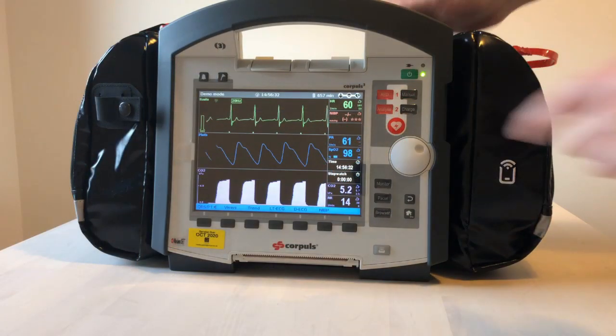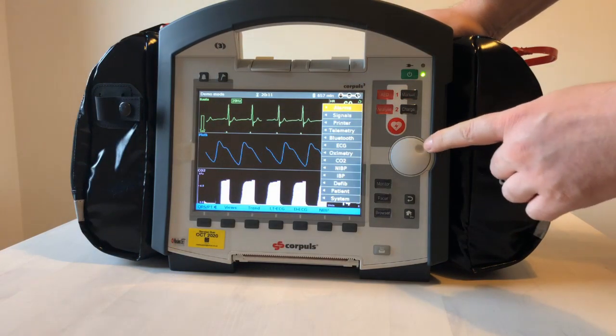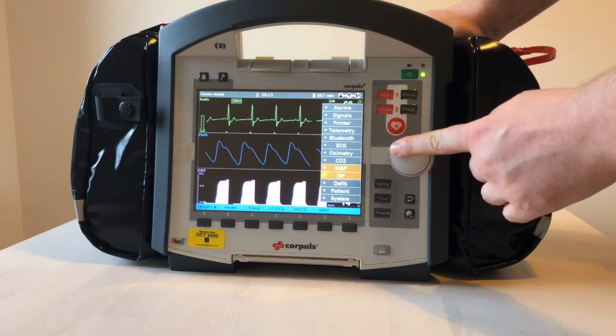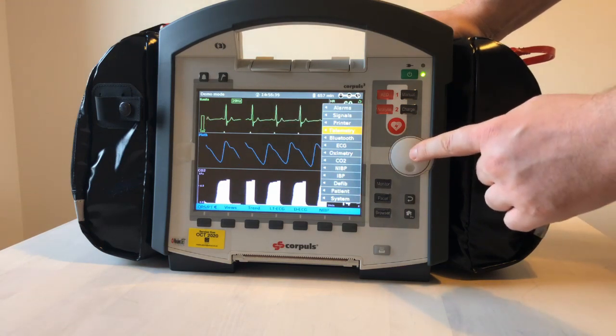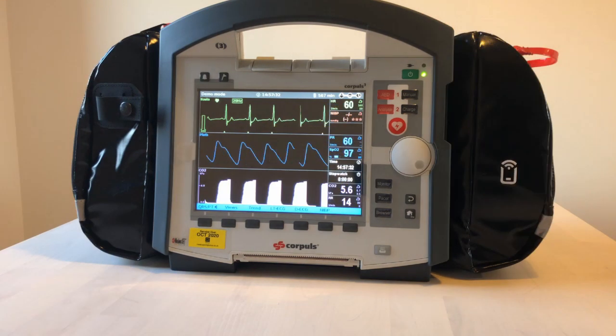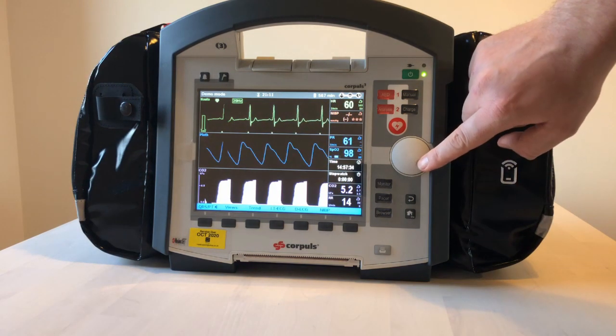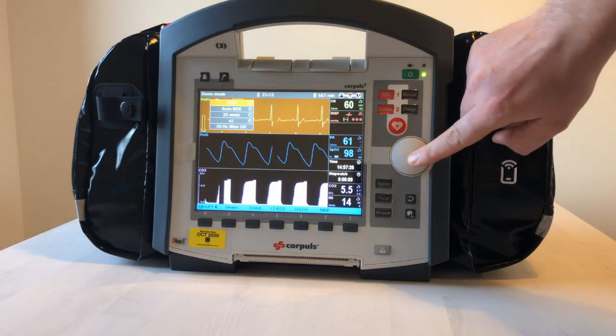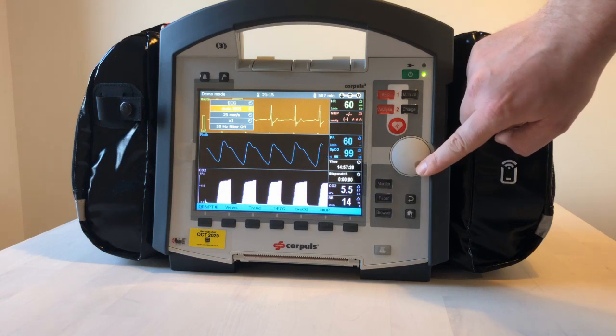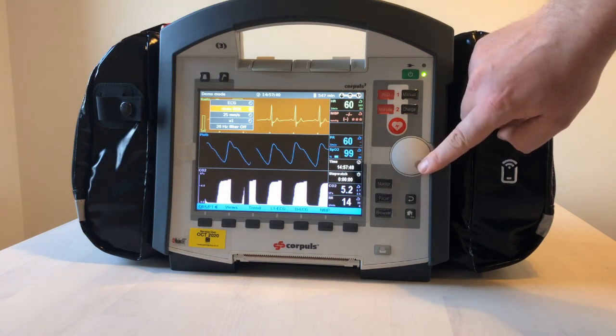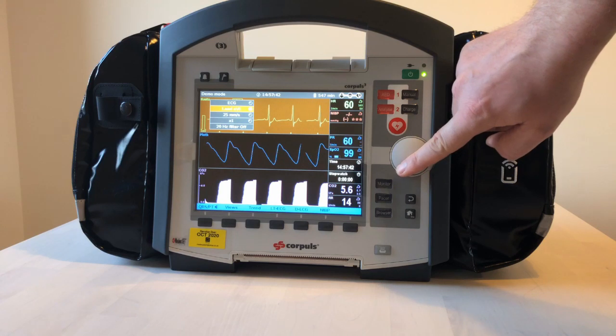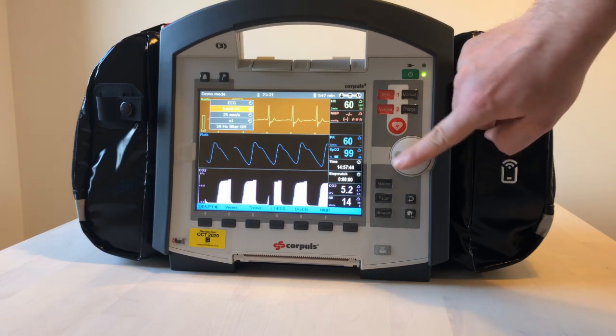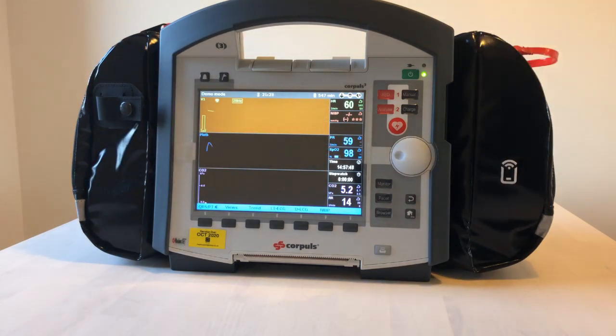To access the settings for the device, press on the centre of the jog wheel. There are no patient monitoring functions in this menu. To change what is displayed on the screen, you can scroll to the appropriate item that you wish to change and push the jog wheel to enter the submenu. And here, you can edit what is displayed. When you restart the device, these changes will revert back to their default settings.